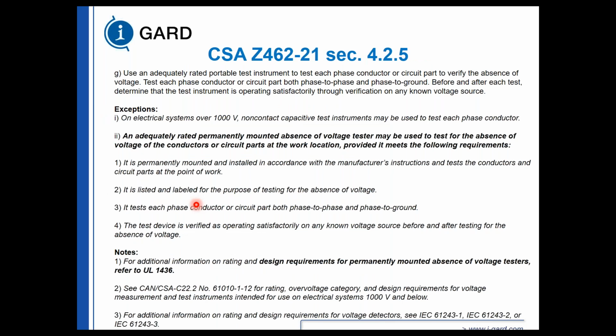CSA Z462-21, basically the same thing. And we've added more notes over here. Design requirements for permanently mounted absence of voltage testers refer to UL 1436. It still has a meter, so you have to test to CSA and UL 61010, but for specific reasons, 1436 is a standard that all absence of voltage testers must abide by.